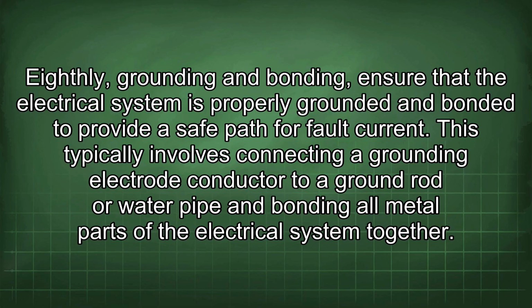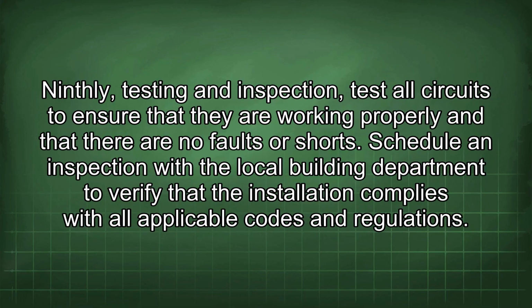Eighthly, grounding and bonding. Ensure that the electrical system is properly grounded and bonded to provide a safe path for fault current. This typically involves connecting a grounding electrode conductor to a ground rod or water pipe and bonding all metal parts of the electrical system together. Ninthly, testing and inspection. Test all circuits to ensure that they are working properly and that there are no faults or shorts. Schedule an inspection with the local building department to verify the installation complies with all applicable codes and regulations.